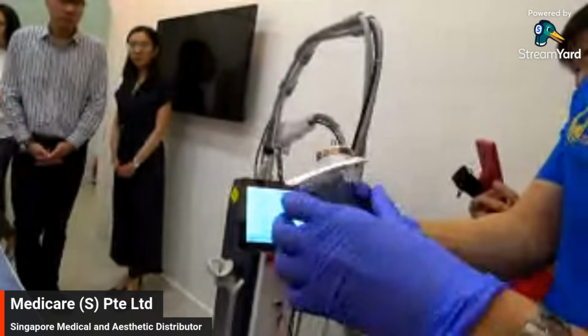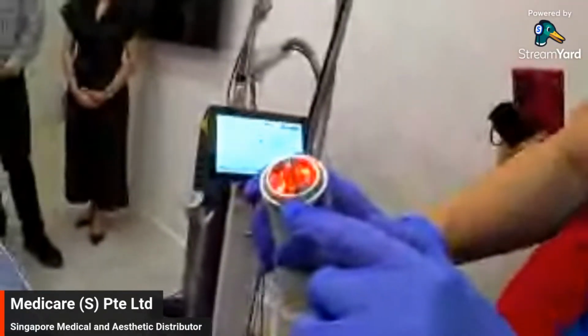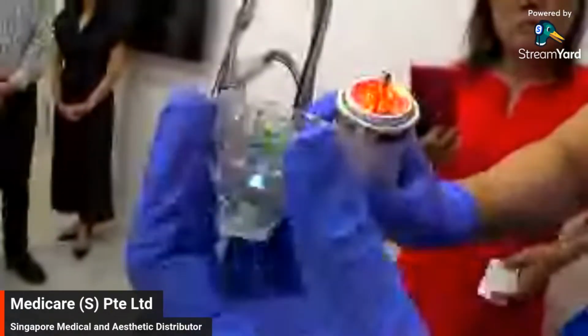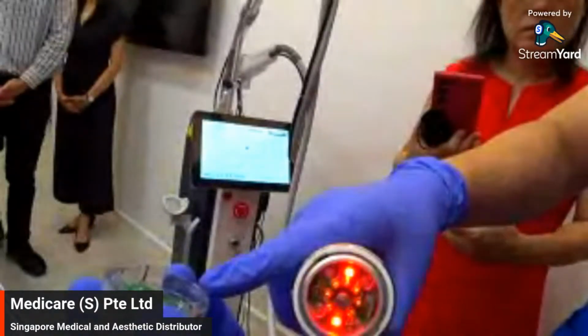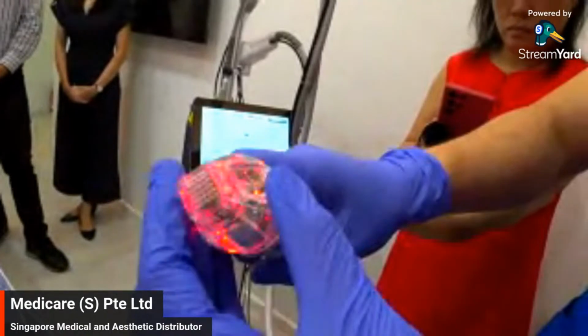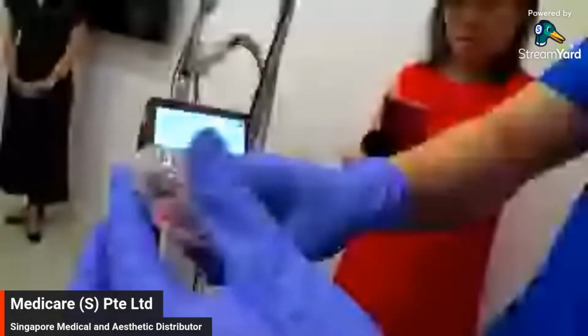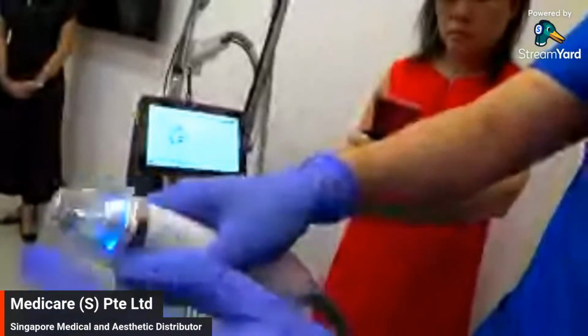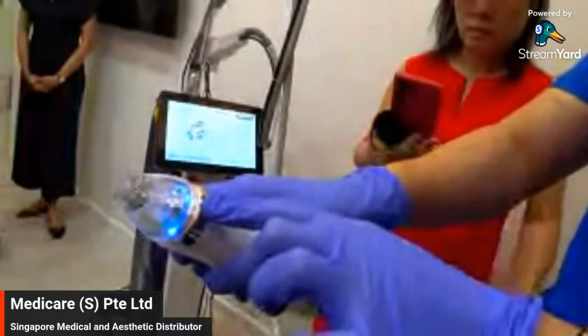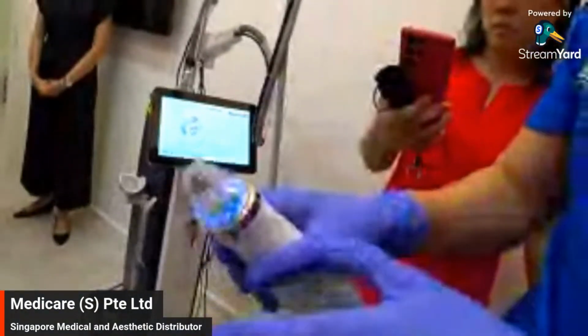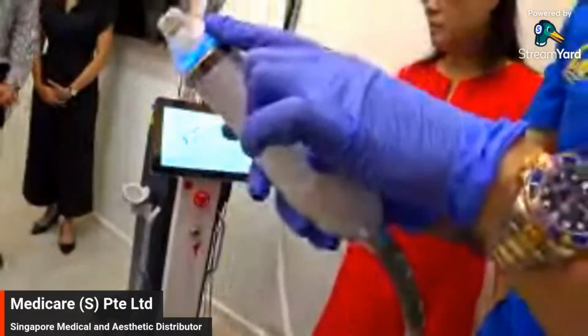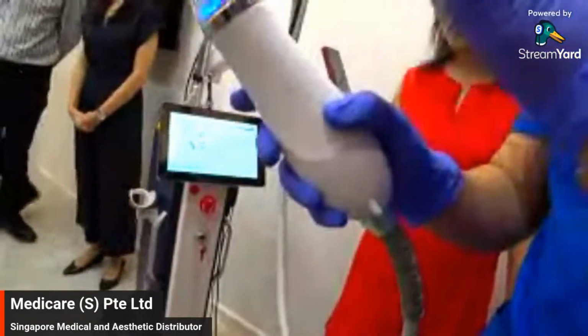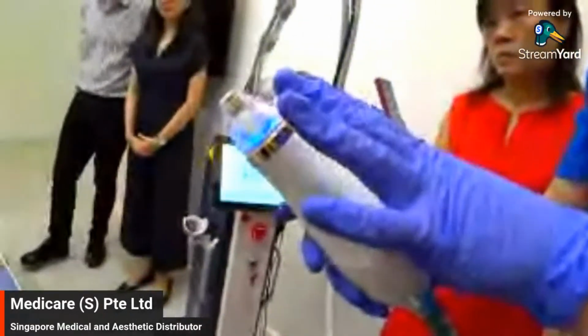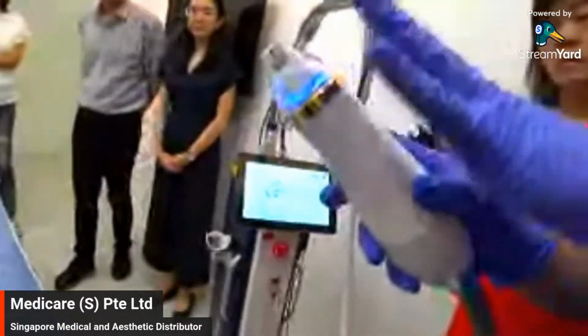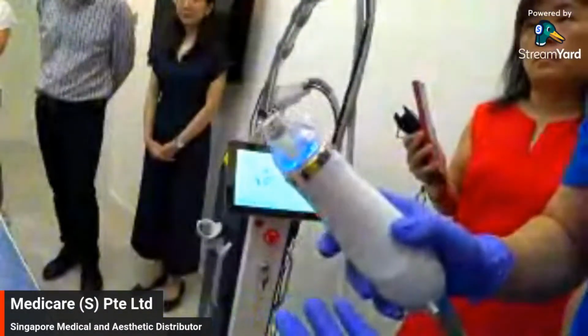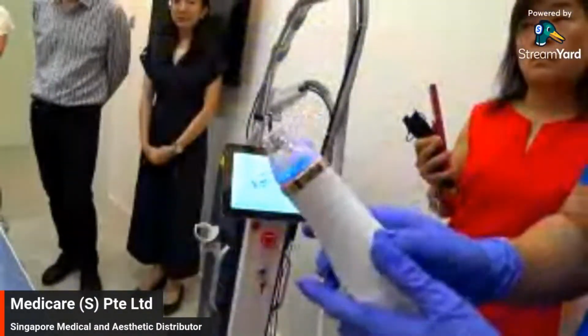As you can see here, there's a big groove and a small groove. There are corresponding grooves on the needle tip. So you fit it in, and then you twist. When you twist it, if you're locked in, the light will change and it will detect. Because the needle tip is exposed to blood products, every needle tip is single use and cannot be used for different patients.